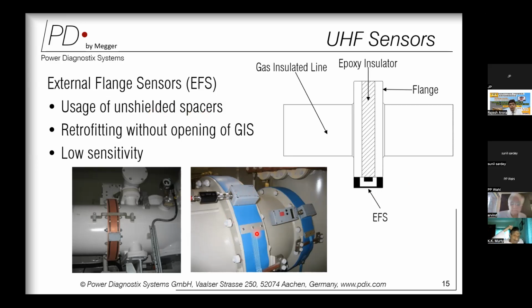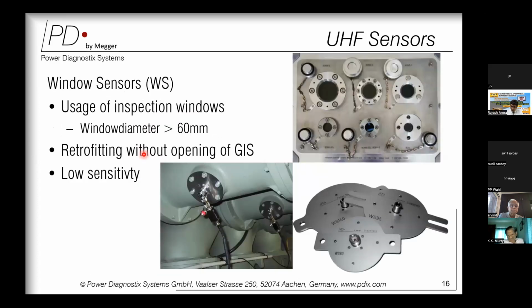So there are spaces which are unshielded and which offer certain openings. These sensors are placed onto this opening, because if it is a shielded metallic portion, then the UHF signal will not radiate out of the GIS. Hence it has to be placed onto these unshielded portions of the GIS, from where it will pick up the signal and feed it to a measuring instrument. Since it is an external arrangement, it offers lower sensitivity.